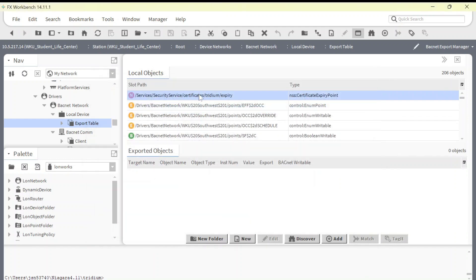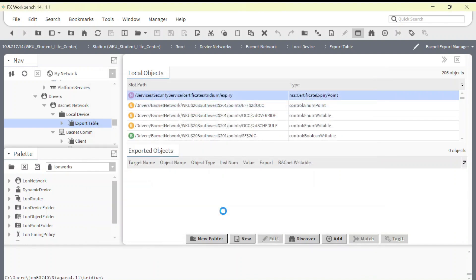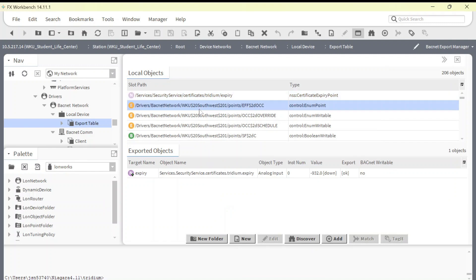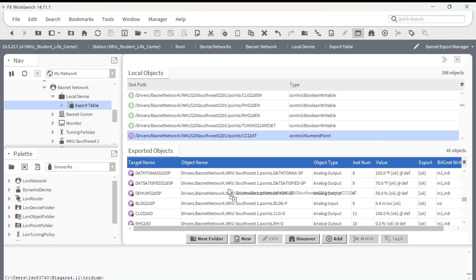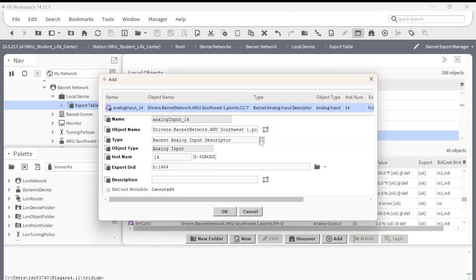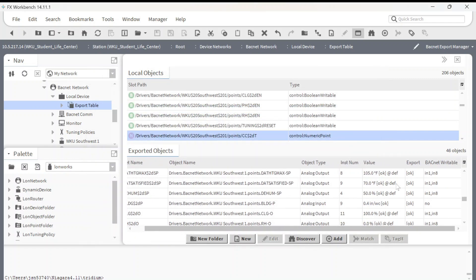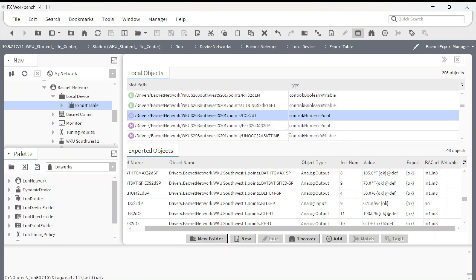We're just bringing in all of the points on the system initially. I do want to point out something you need to pay attention to: if you are going to make these points writable, there is a particular way you've got to pull those in. Each time you grab one of these points and drag it down, you're going to get a pop-up window — that is critical. Make sure the points pulled into your Tridium Jace are writable before you even try to do this step.